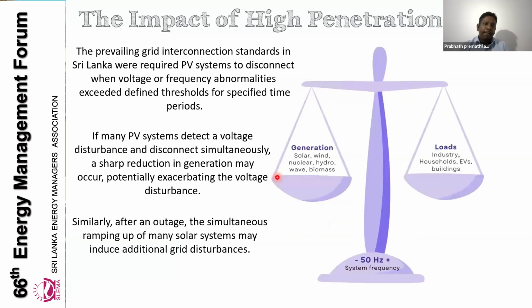The next one: up to last year, the prevailing grid interconnection standards in Sri Lanka required PV systems to disconnect at a voltage disturbance or frequency disturbance. So when there is a fault or a generator tripping, and there is a voltage or frequency disturbance, if the solar PV generation is disconnected simultaneously, again we have a generation drop, and that can worsen the situation.